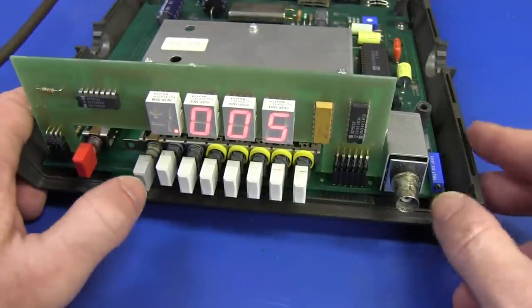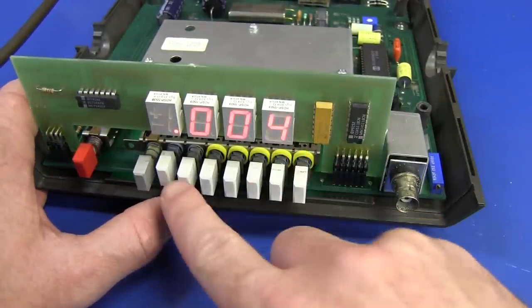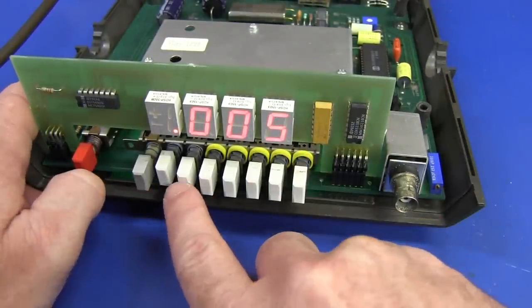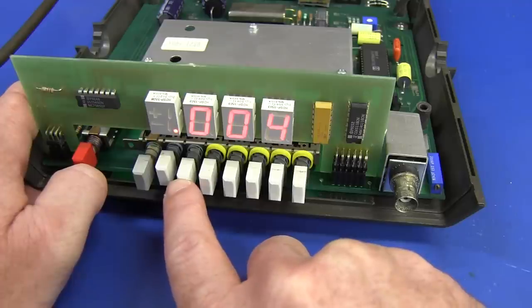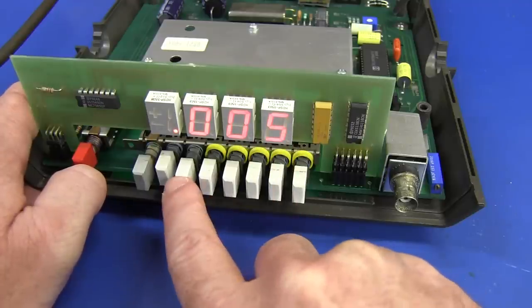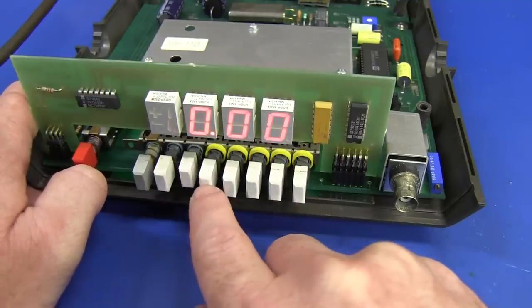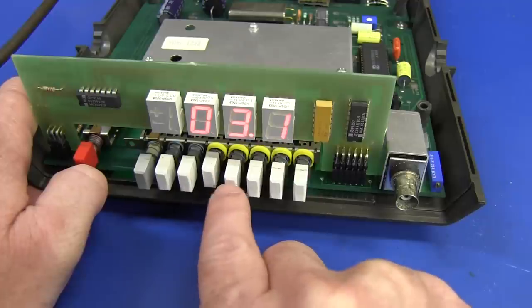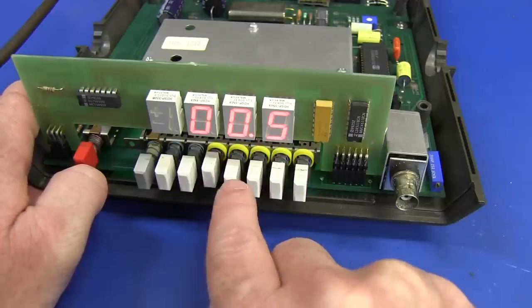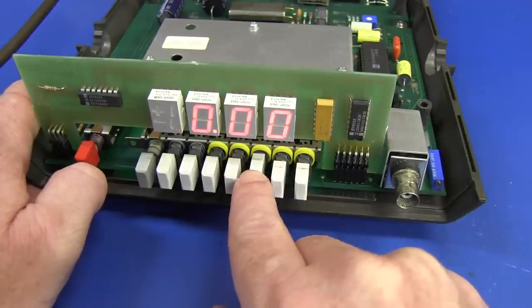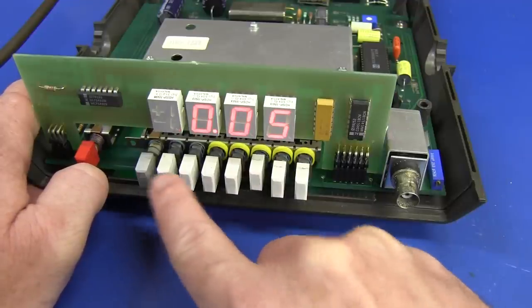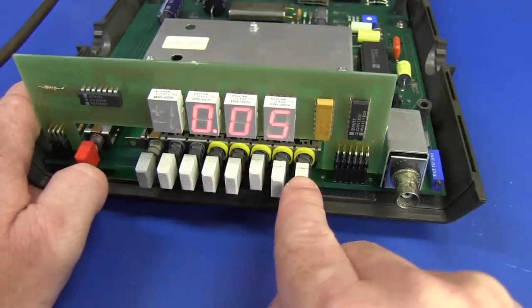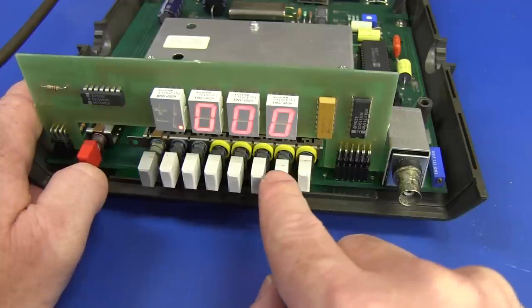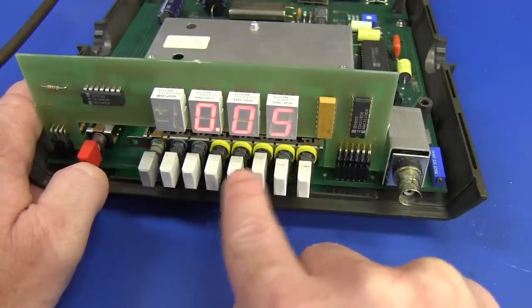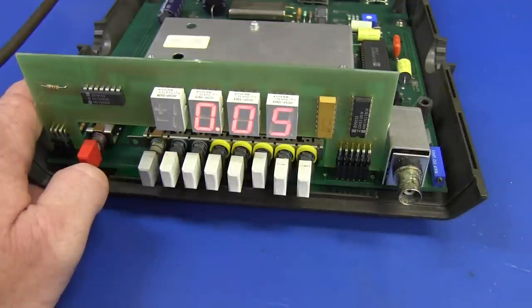Now, as you may have seen before, it looks like we're not getting a zero reading on some of these ranges. That's the 1 nanoamp range there. So we're getting like 5 picoamps there with no input. And others are showing zero, not a problem, but we're getting 5 on that as well. So it looks like we're getting 5 on those alternate ranges, and we'll probably get 5 on this one. No, there we go. So on that range, we're getting 5.